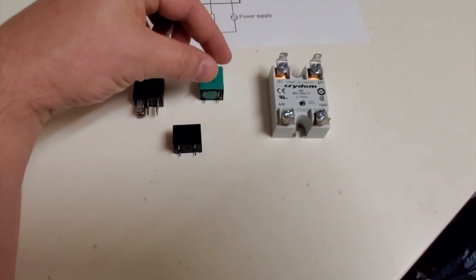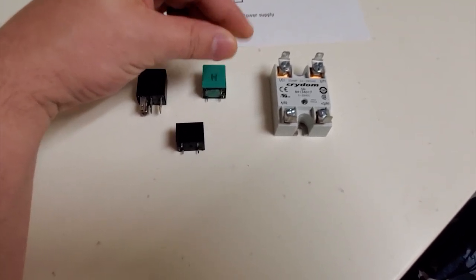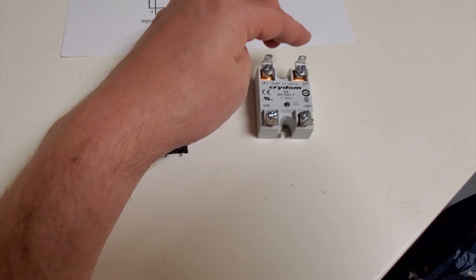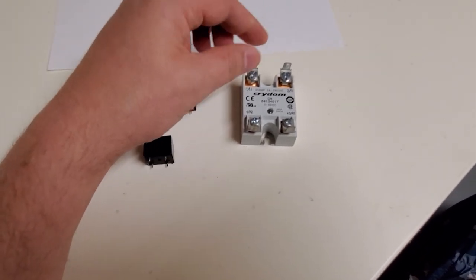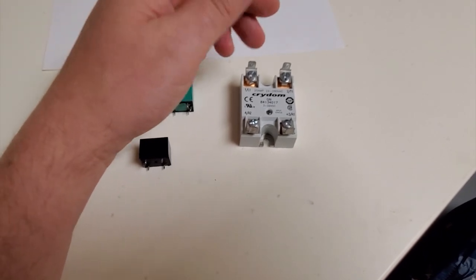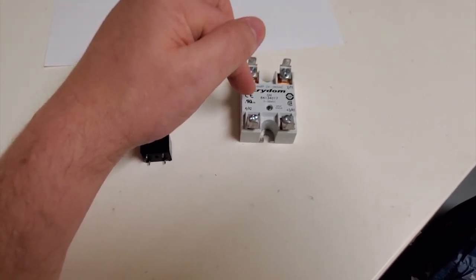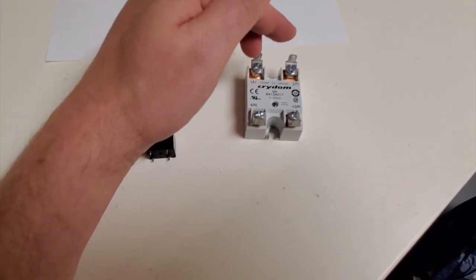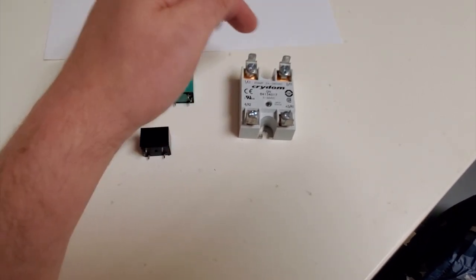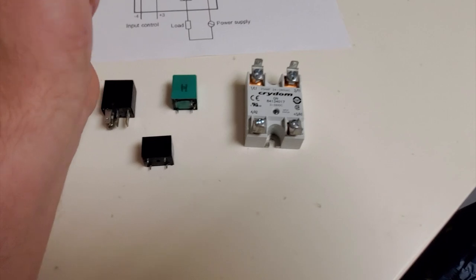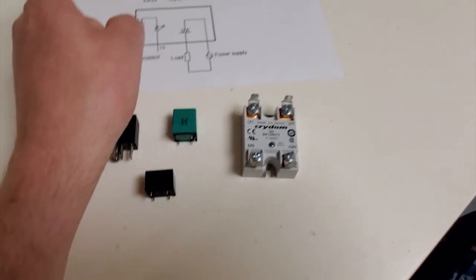So when you're checking this side to see if it's active, then what you would do is you'd put it on voltage, AC voltage, and you would check it. And there should be only one to two volts difference between these two pins. And that is how you know if it's actually turning on your load or not.